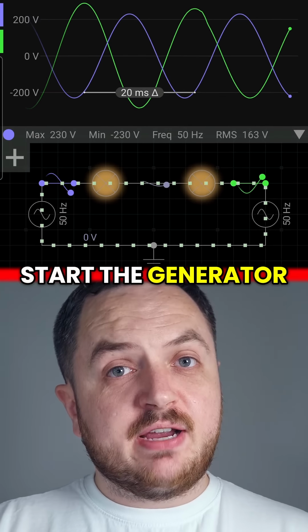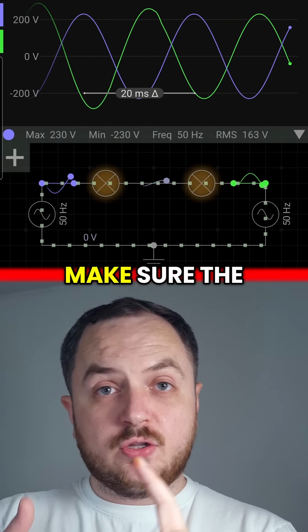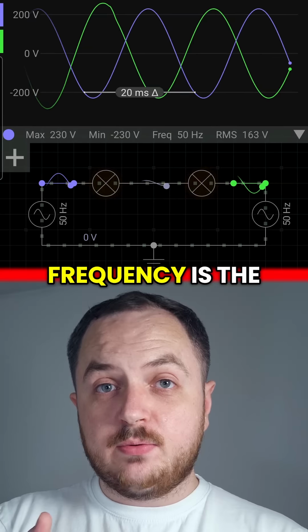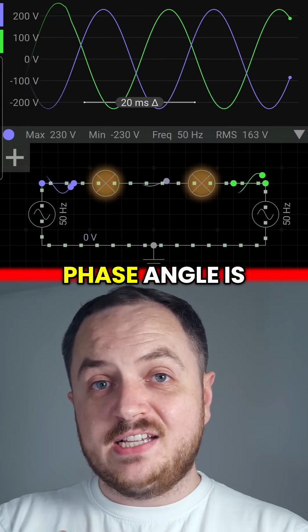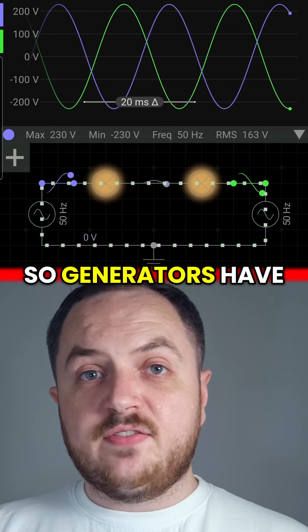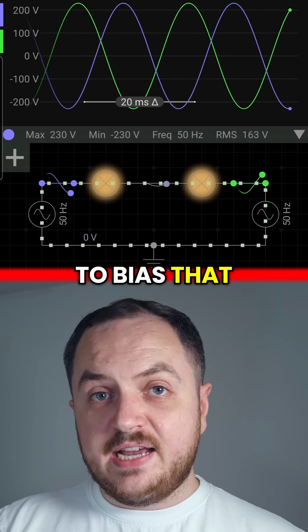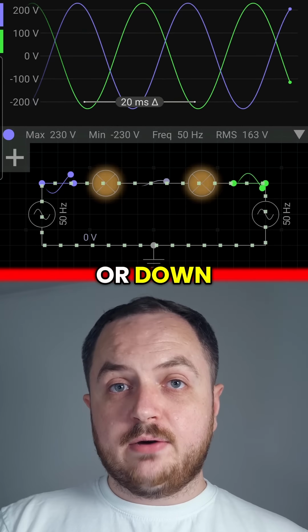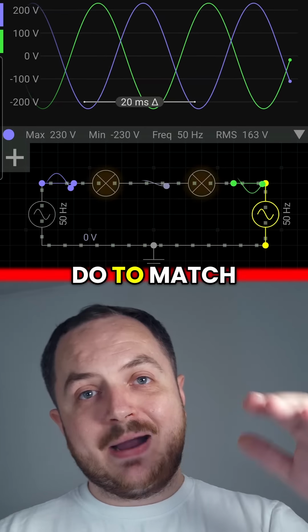So now we start the generator up. What we need to do is we need to make sure the voltage is the same, we need to make sure the frequency is the same, and we need to make sure the phase angle is the same. So generators have an AVR on them. We need to bias that AVR so that the voltage goes up or down depending on what we need to do to match that main supply.